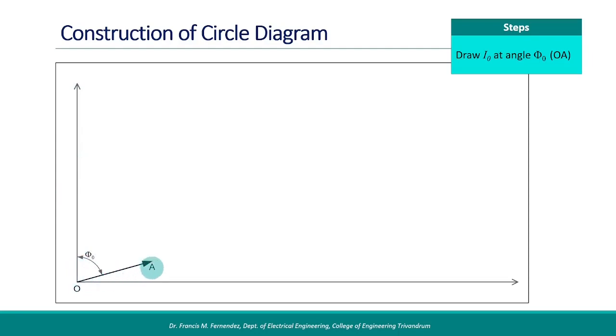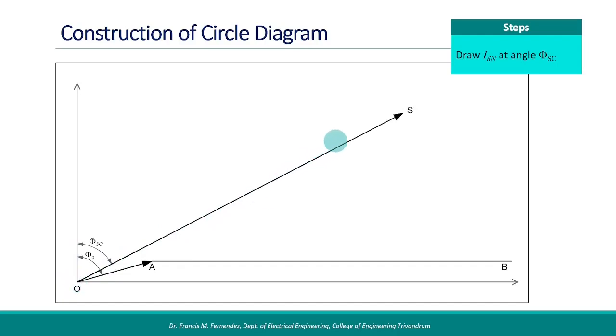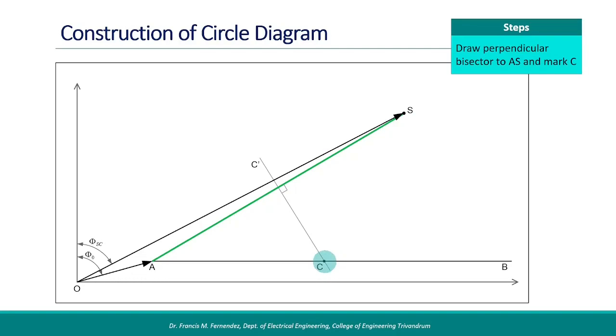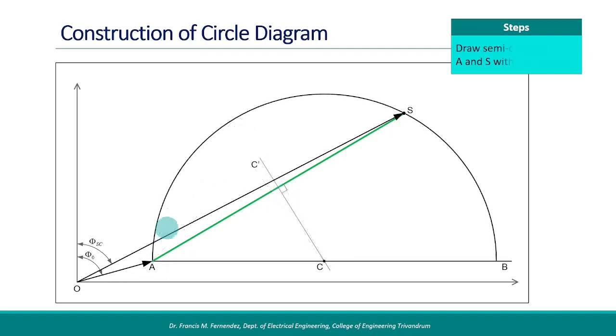OA represents the no-load current. Starting from A, draw a horizontal line AB. Next, the per-phase input current at the blocked rotor state with rated voltage applied, ISN, is to be represented. Draw the line OS counting the current scale at an angle phiSC. Then draw a new line AS connecting points A and S. The next step is to draw a perpendicular bisector to AS. This bisector meets the horizontal line AB at point C. Draw a semicircle with C as center and CA as radius. This circle represents the locus of current for the motor under different operating conditions.